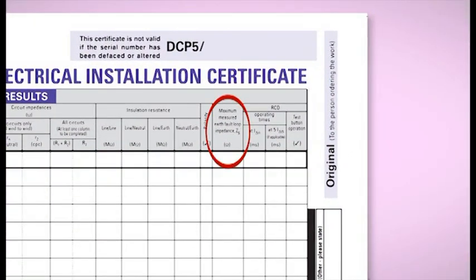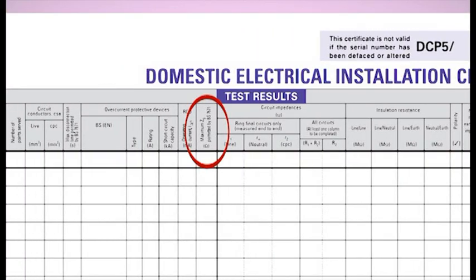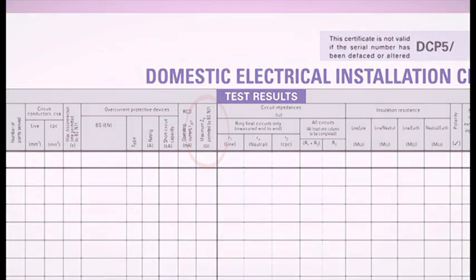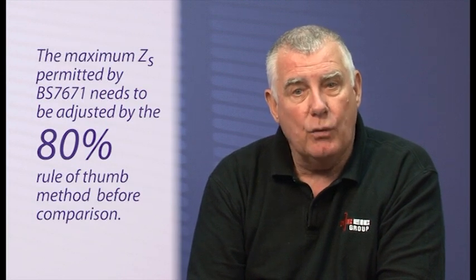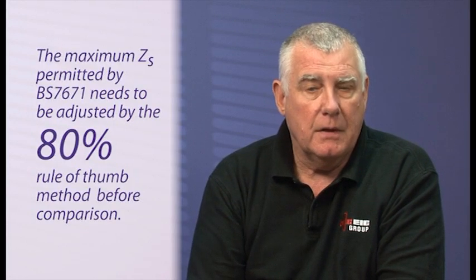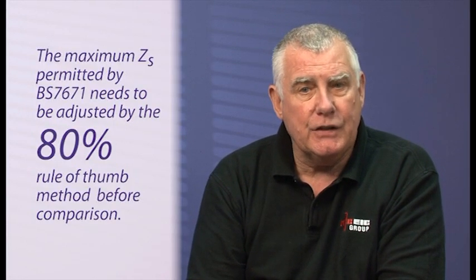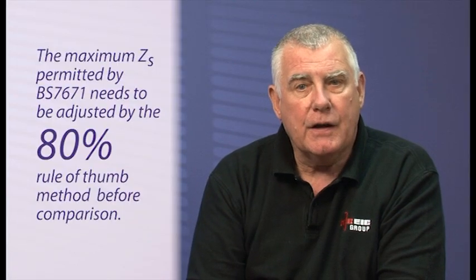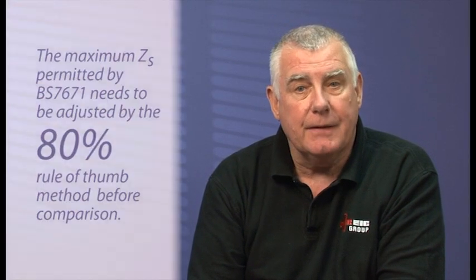Next, we have maximum measured earth fault loop impedance. And this is another box which can cause problems, especially when compared to the box maximum ZS permitted by BS 7671. Usually, what happens is the electrician takes a reading, sees that it's lower than the maximum allowed ZS from the regs and thinks everything is fine. Unfortunately, the maximum ZS needs to be adjusted by the 80% rule of thumb method before comparison. This allows for the difference between conductor temperature during normal operation and the colder conductor temperature during testing.